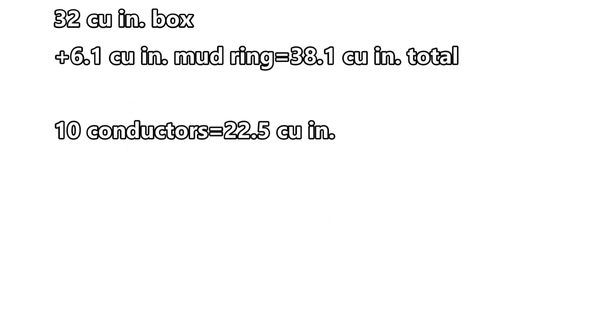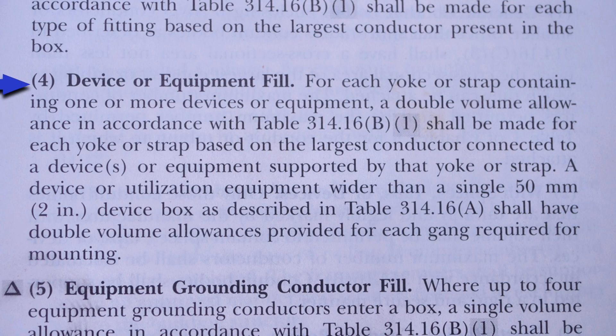So we now have 22.5 cubic inches accounted for with the 10 conductors. So far we have a 32 cubic inch box and a 6.1 cubic inch mud ring for 38.1 cubic inches total, and we have 10 conductors which equals 22.5 cubic inches. We're doing real well so far. Now let's find out how much we have to allow for the switch and the receptacle.